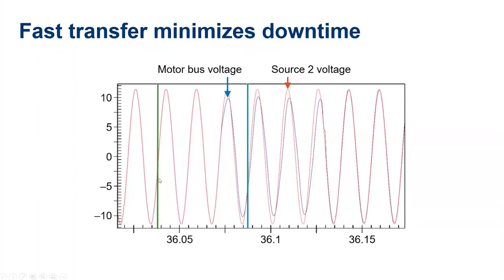synchroscope view. If we go and look at the time domain of the same event, here we would get the signal to start the transfer. Here we are looking at, in red, the voltage on the source we are trying to transfer to, and in blue we see the voltage on the motor bus. So here we receive the signal to start the transfer, and we immediately send the open command to the breaker that connects us to source 1. And so there is a delay there, to send the signal to the breaker and for the breaker to actually open.